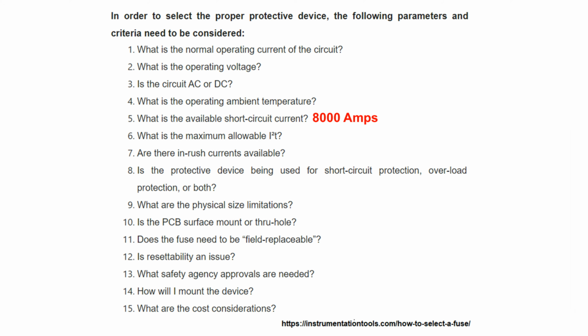Most of your residential branch circuit breakers will be rated for 10,000 amps. That means the overcurrent protective device can instantaneously, in quotes, open up and interrupt the very high current flow of a dead short without the internal contacts being welded together due to the arc that's jumping across them as they open. Most residential main breakers will have an AIC of 22,000 amps.